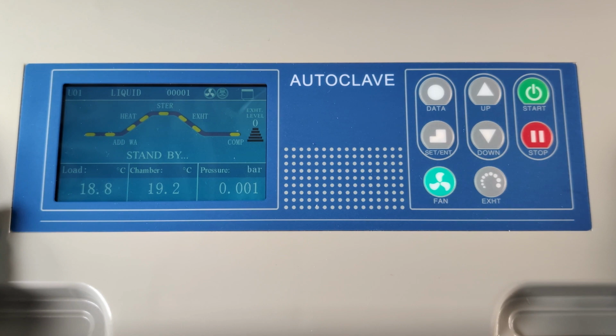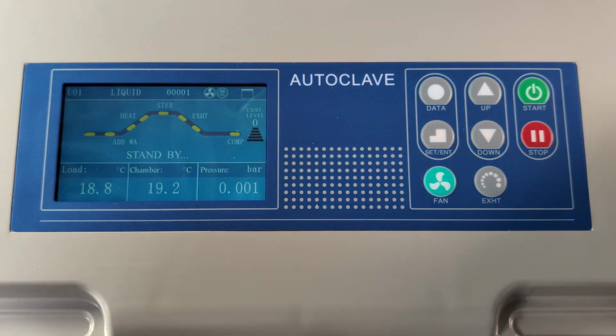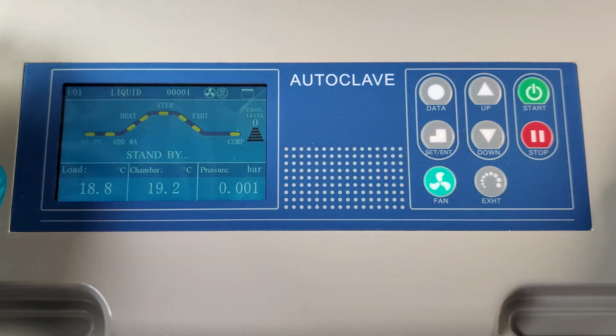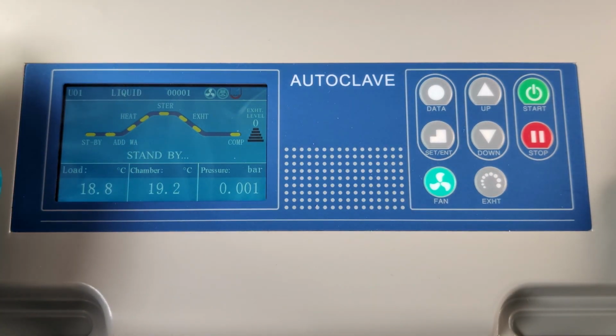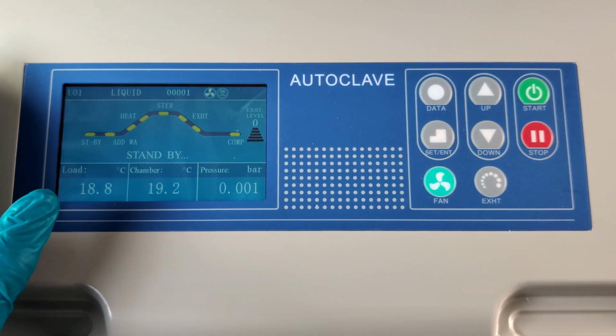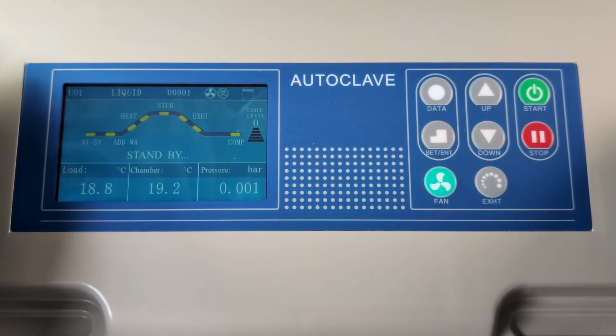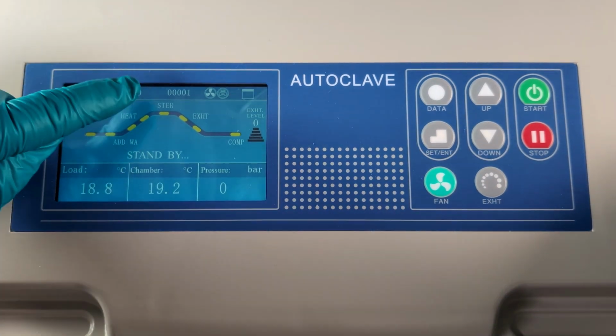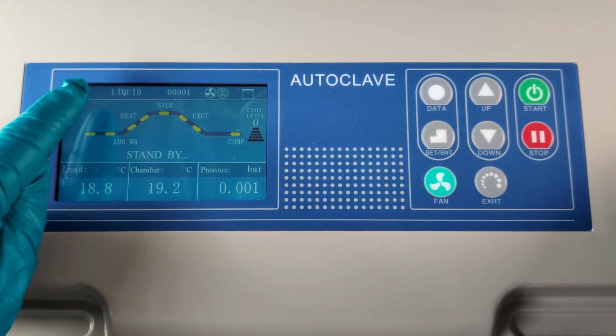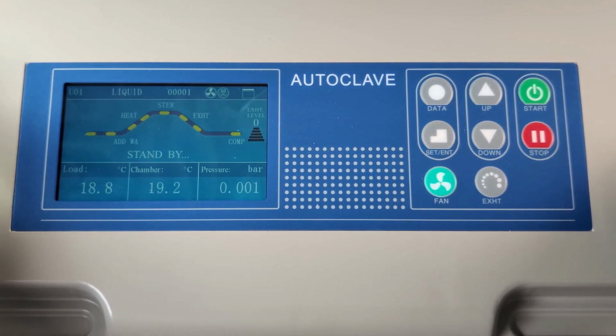It's what's known as timed-free steaming, and at this point, all the steam replaces all the air, so you have a saturated steam enclosure, which is what you need for sterilization. Then when the vents close, you can build up the pressure like a pressure cooker, and you get to the sterilization stage, which on this program is set to 121 degrees centigrade.